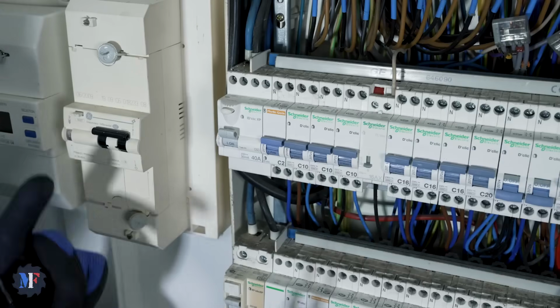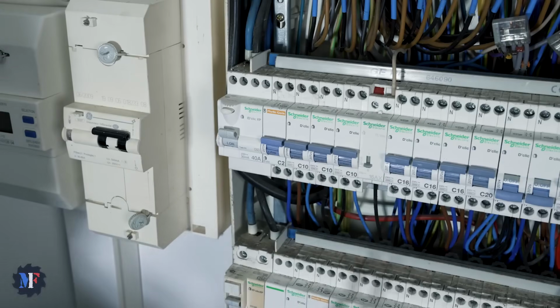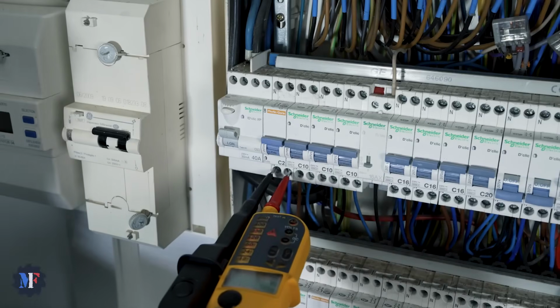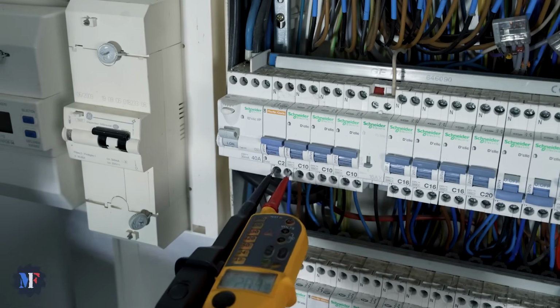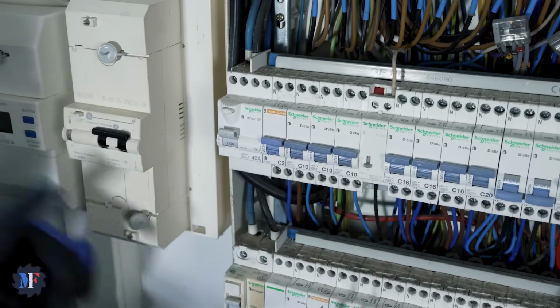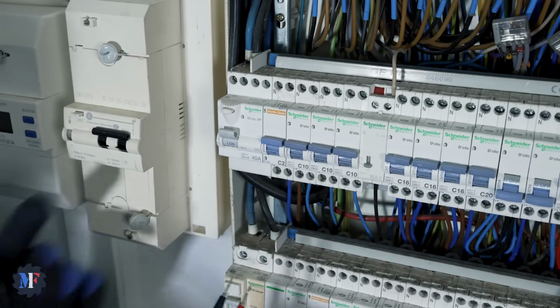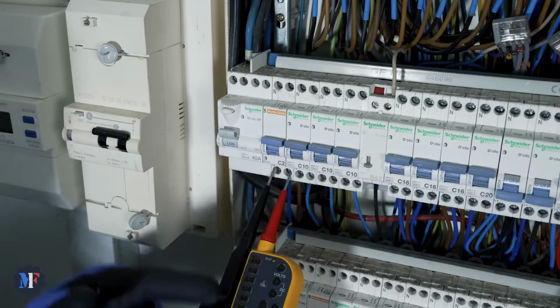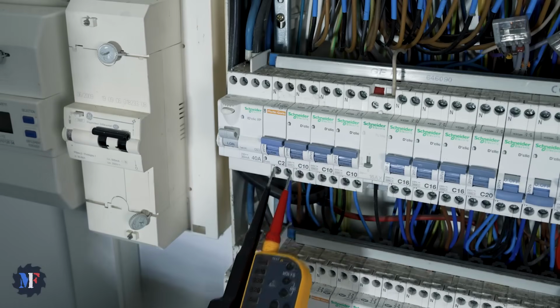Here, the goal is to turn off the breaker for safe work. On the panel, I'll show you that there's definitely current, 230, 234, 235 volts, so we turn off the breaker to work safely. After turning off the breaker, we use a voltage tester to confirm there's no current.